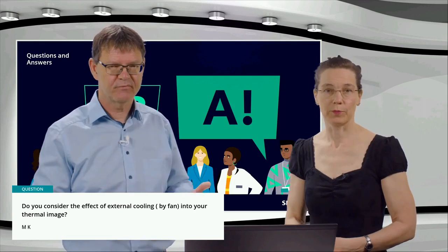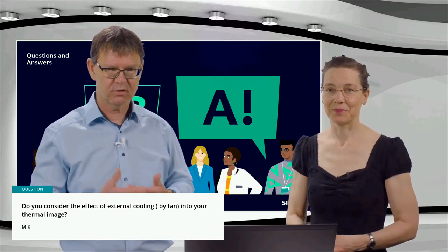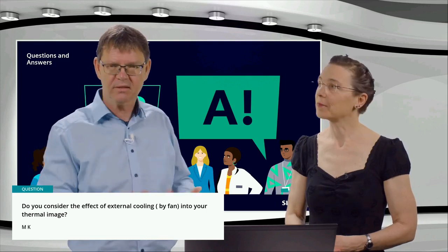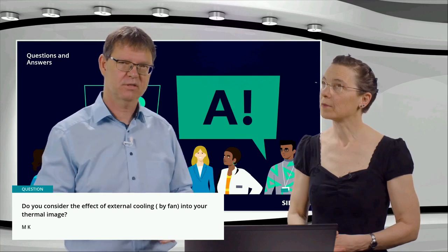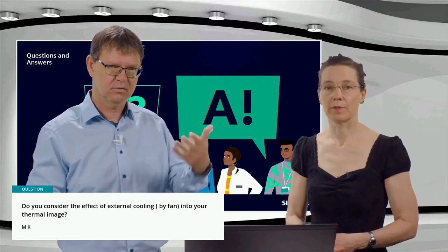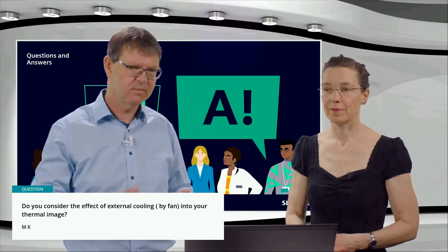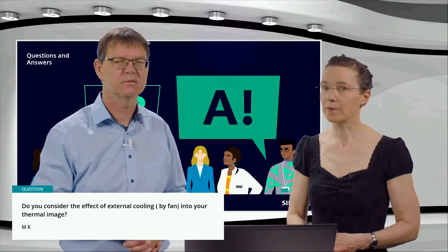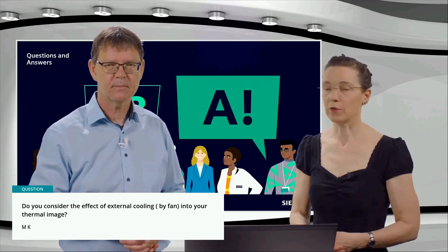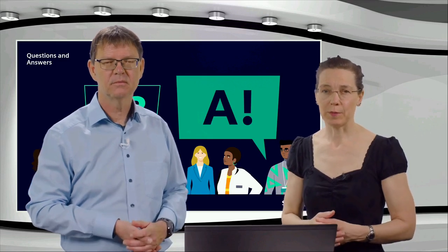Perfect. Thank you. So if you have permanent external cooling which is not connected to the rotor movement, then you can assume the same time constants for running and for standstill, because the cooling effect is the same. Or maybe it's a little bit less, then you can also adapt this with different time constants. Thank you, really helpful.